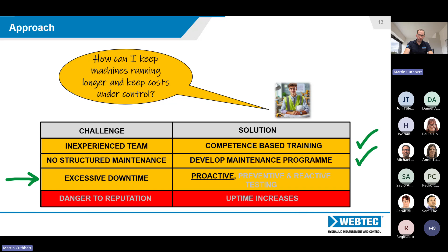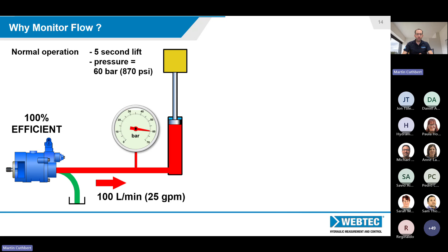So why are we monitoring flow? Typically, flow has been considered quite a difficult thing to measure in comparison with measuring temperature or pressure. But if we just look at this little example, I think it illustrates it very well. So we've got a pump delivering 100 litres into this cylinder. The cylinder typically takes 5 seconds to travel to full stroke, and the applied load requires a pressure of 60 bar. Now, if a fault occurs on that pump and the pump is leaking or is particularly inefficient, particularly worn, if we were then to run that pump again at only 50% efficiency and it's only delivering 50 litres of flow into the cylinder, we're still lifting up the same load. It still has the same operating pressure of 60 bar, but it takes twice as long to lift it up.